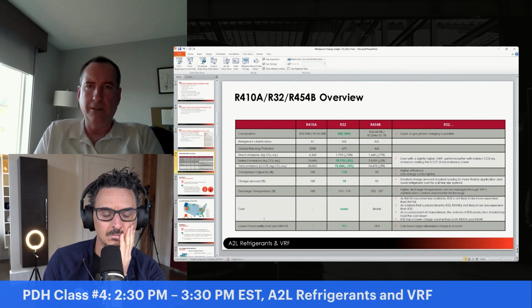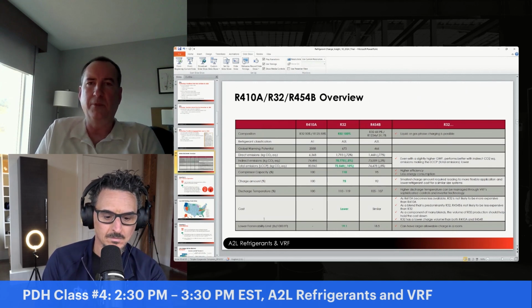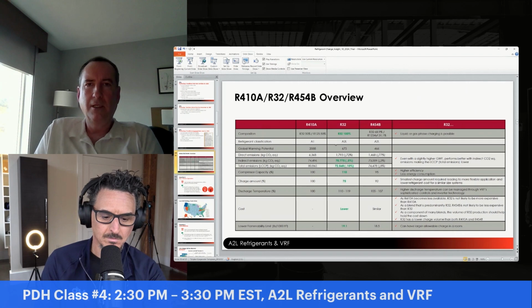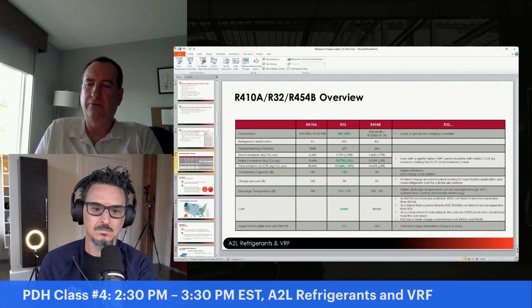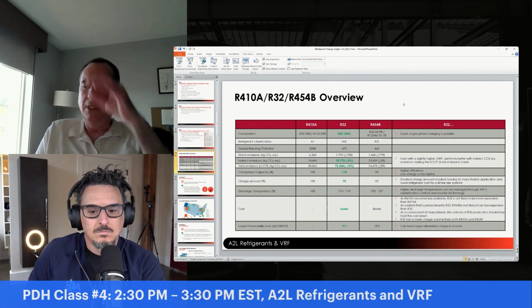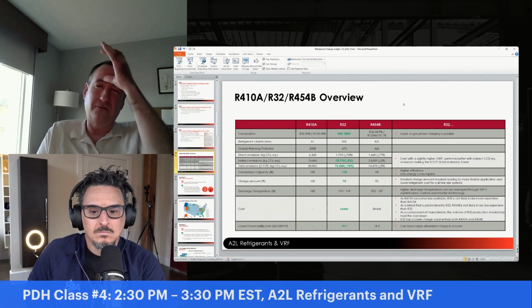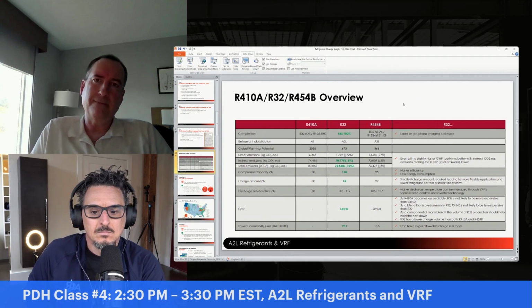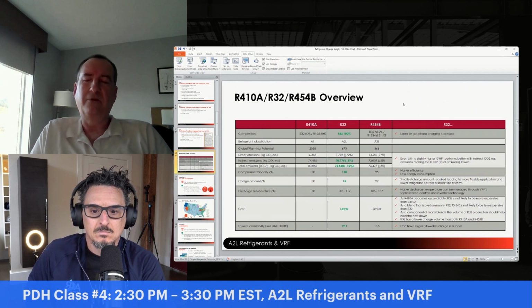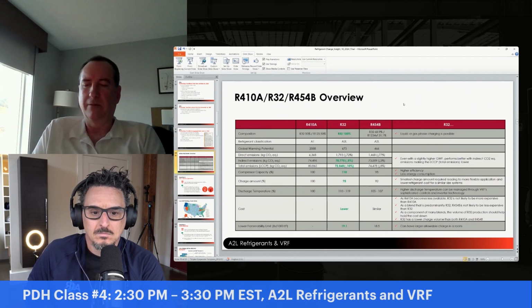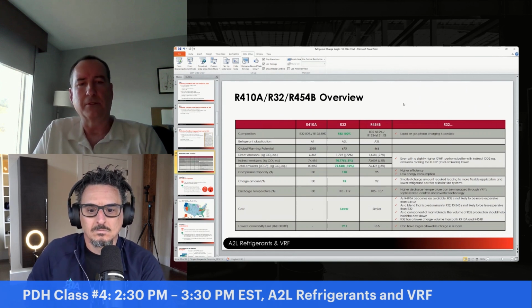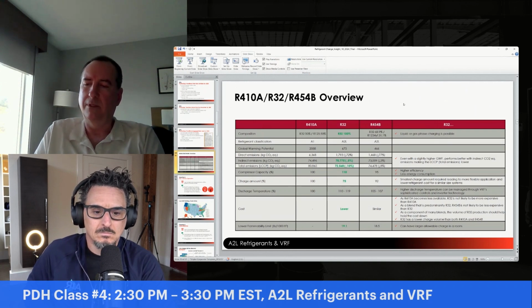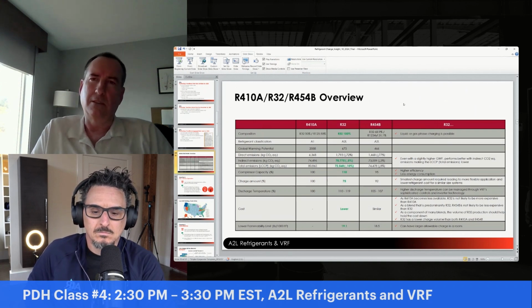R32 fits in with the GWP limit of 700, coming in at 675. Since it's classified as an A2L refrigerant, it is of course flammable, but it's considered very manageable. It's got a very low burning velocity, very low heat of combustion, and a really high auto ignition temperature. So for us, we think it's a good choice.